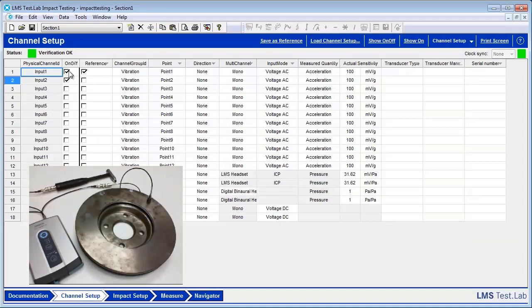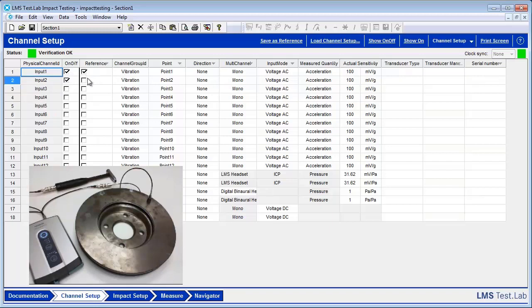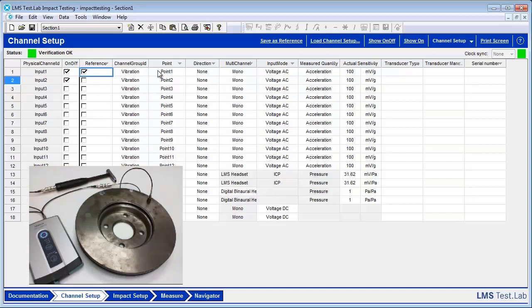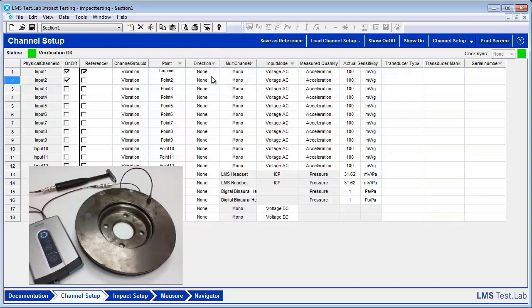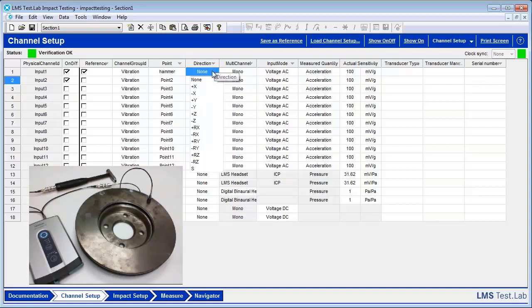Within Channel Setup, we want to make sure that the channels we're using are on. We also want to make sure that our reference channel is the hammer. In this case, that's going to be Channel 1. Then we can come over here to Point ID, and we can change this if we'd like. Our next option is Direction. If we wanted to animate our geometry after we calculate our FRFs in this measurement, then changing the direction is important. For this case, not so much.